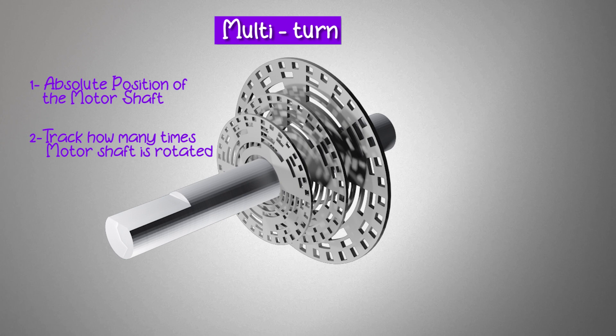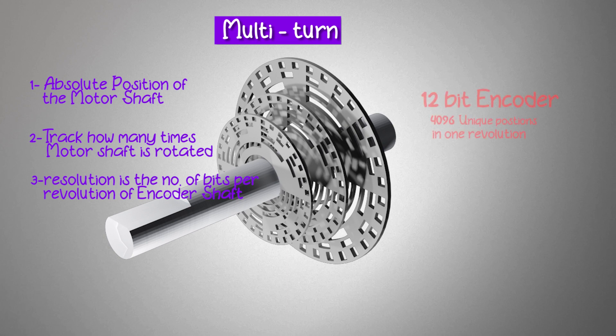The resolution of these encoders is usually specified as the number of binary bits available per turn. For instance, a 12-bit encoder would have 4096 unique positions, similar to 4096 pulses per revolution in the incremental encoder as discussed in the previous video.